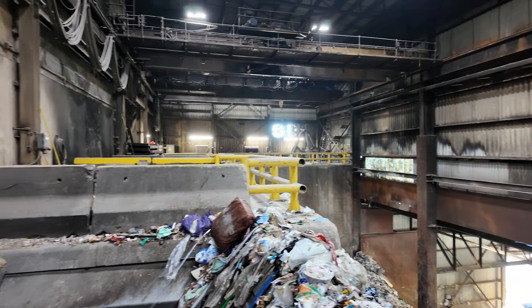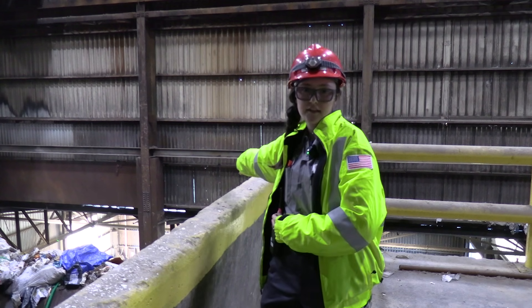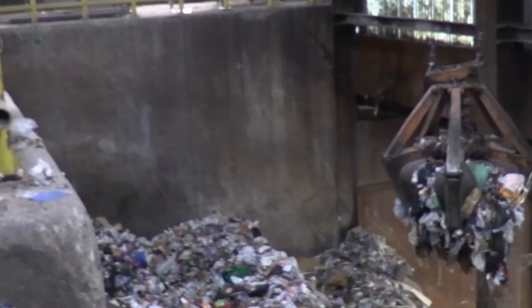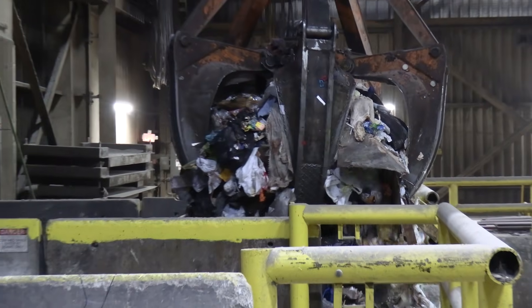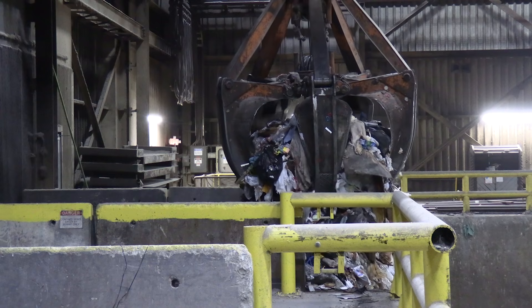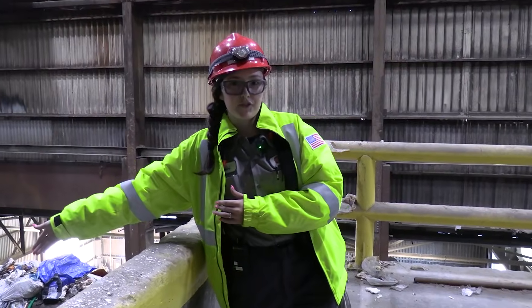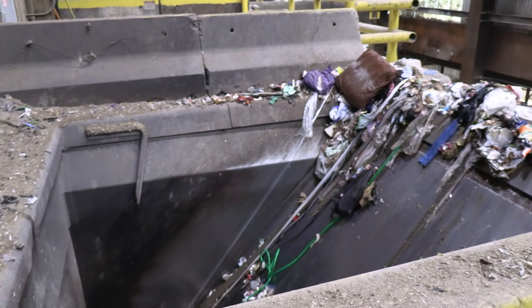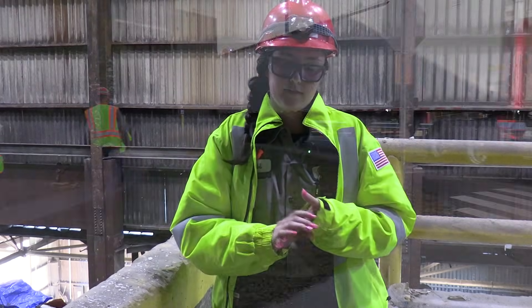We have moved over to the feed hoppers. This is our first boiler. The pits are on the other side of this incline. The crane operator brings a load of refuse and does a 70-30 dump, so not all the refuse makes it in at once — some goes back into the pit. They drop it down and it slides down this feed chute, which arches and has sections of mechanics that move to allow the trash to evenly go through without overwhelming the boiler with too much trash at once.